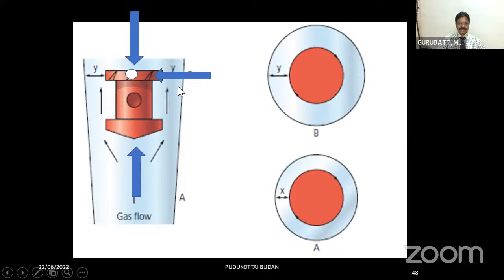So the other thing is the annular space. You can see the annular space between the outer margin of the bobbin and the inner margin of the flow meter tube. This space is called the annular space. In the lower flows, the annular space is small. As you go up, the annular space keeps increasing, so the orifice keeps increasing. That's why these are also called variable orifice flow meters. And the other important thing is that the pressure drop across the bobbin is always constant. That's why these bobbins and flow meters are also called constant pressure flow meters.